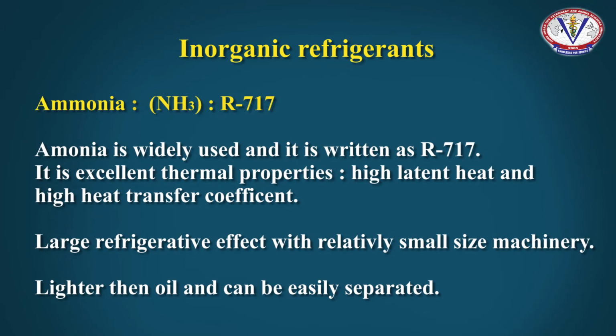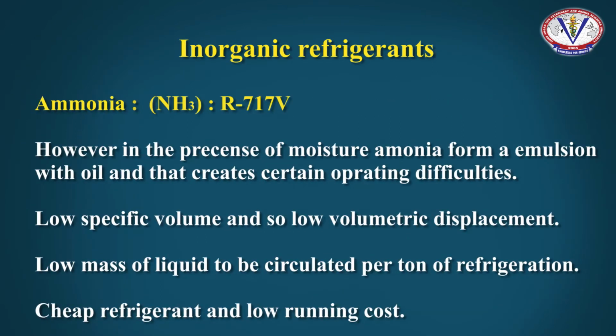Under the inorganic refrigerants, ammonia is widely used and it is written as R717. It has excellent thermal properties, high latent heat and high heat transfer coefficients, large refrigerating effects with relatively small size machinery, and is lighter than oil, so it can be easily separated. However, in the presence of moisture, ammonia forms an emulsion with oil and that creates certain operating difficulties.